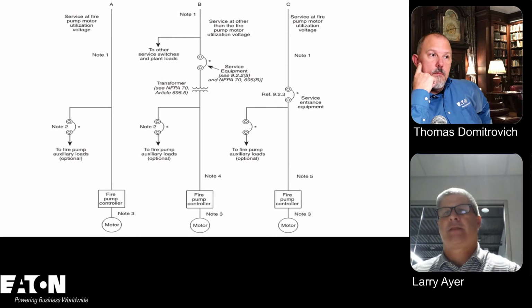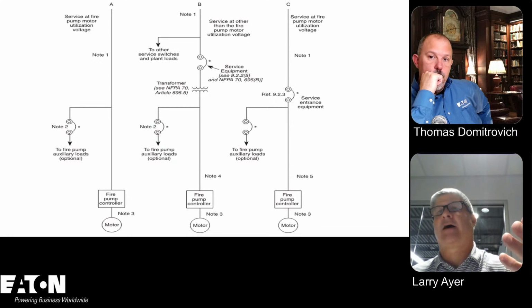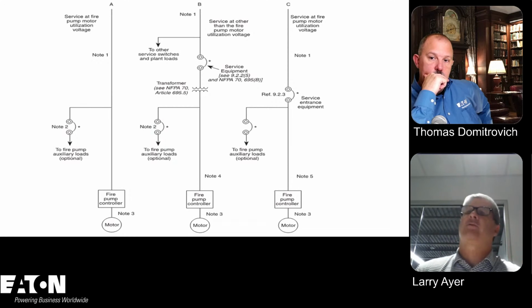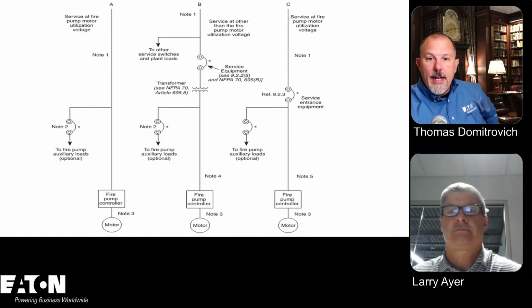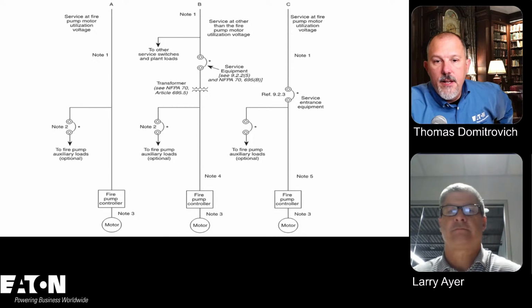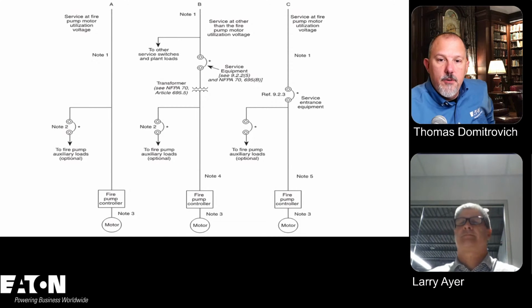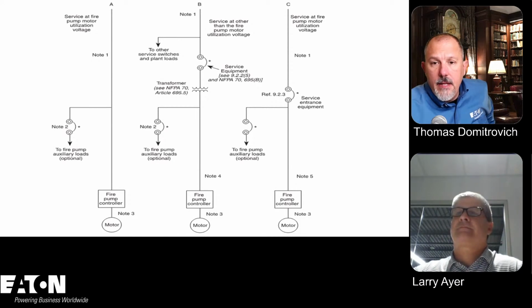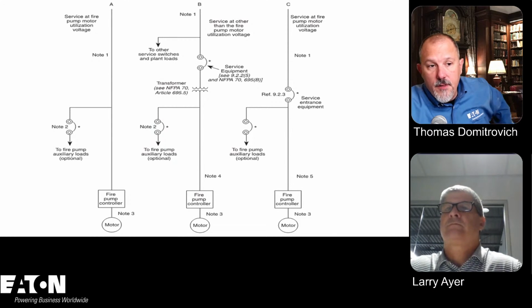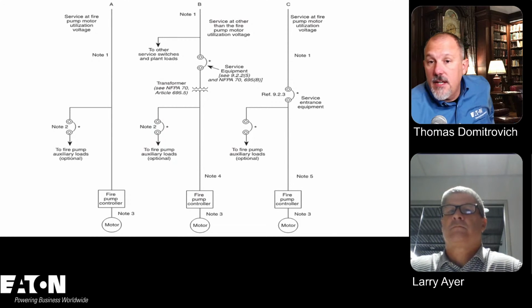In B, you have a transformer, but there's only one disconnect between there and the fire pump controller. And in C, that is a direct feeder. So again, you have one disconnect up to the fire pump controller. Yep. And in each of these, you show the fire pump auxiliary loads coming off the same feed. To the earlier comment in the chat box, that doesn't have to come off of that. It could come from anywhere, right?